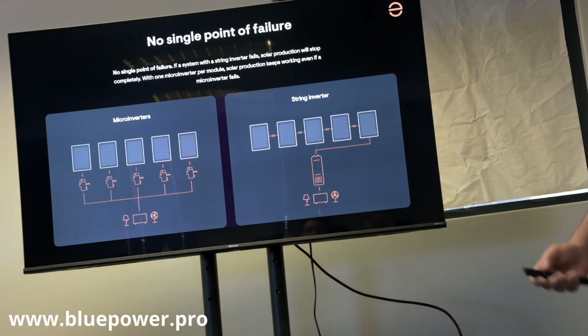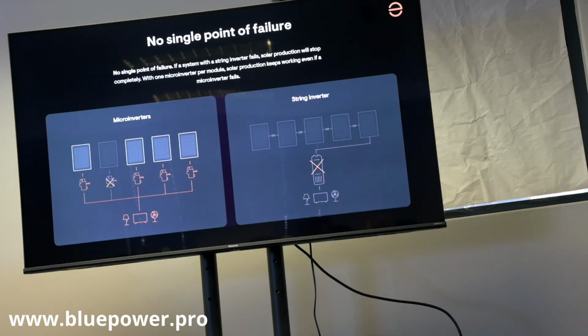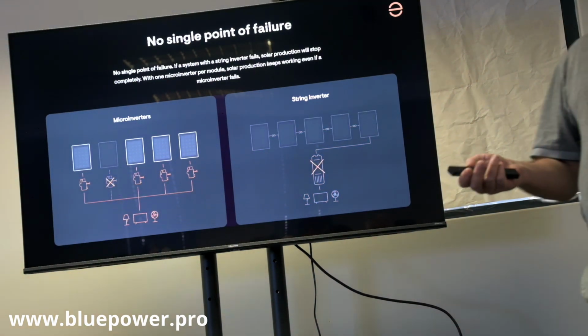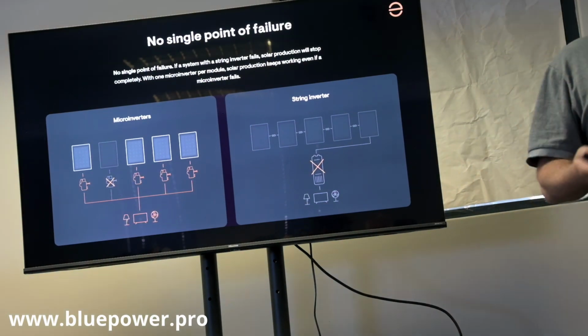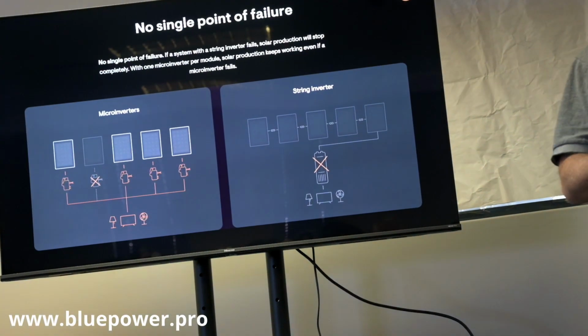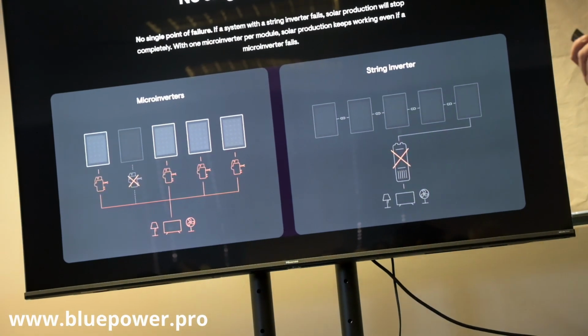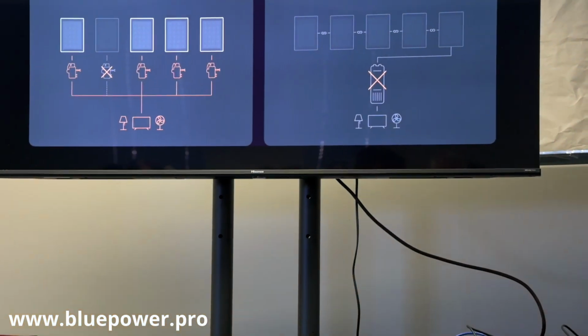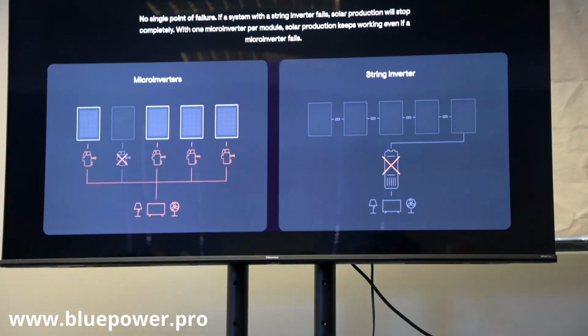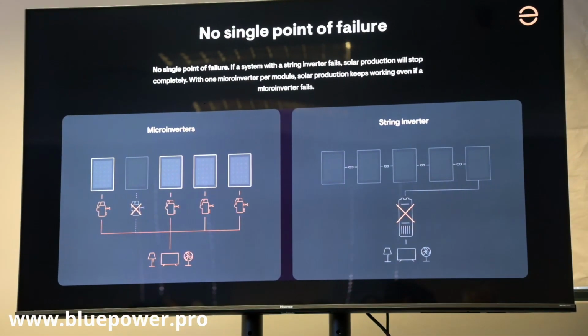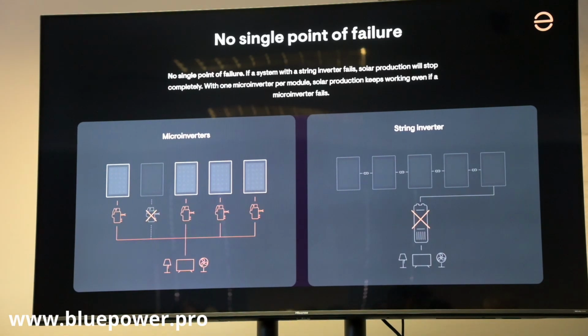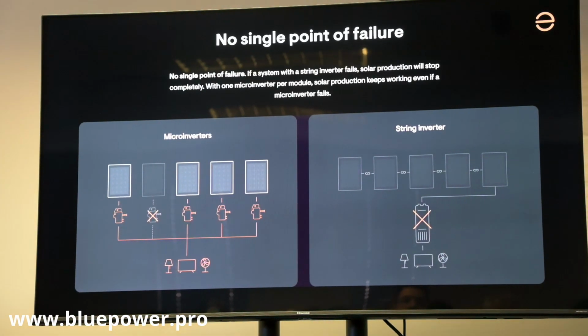If we look at your normal DC string—when you install a DC string and there's any shading, your normal DC or hybrid inverter shuts down because its startup voltage goes below that threshold. Microinverters continue to generate. To give you an idea, a microinverter will start generating with low irradiation of about 200 watts per square meter, because its startup voltage is 25 volts DC, compared to what you need in a whole DC string for that inverter to start up, which is about 120 volts DC.